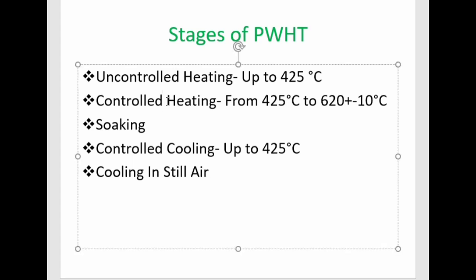The second stage is the controlled heating process, which takes place from 425°C up to the soaking temperature of approximately 620°C. From 425°C to the soaking temperature, the heating rate shall be controlled and conducted in a uniform manner.